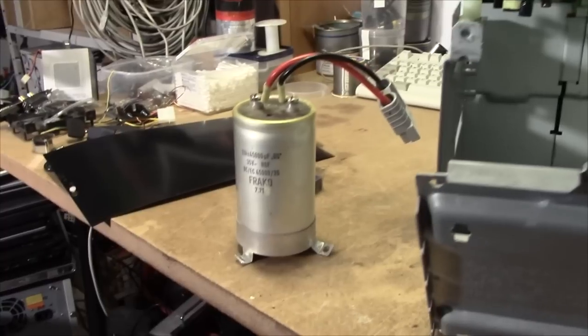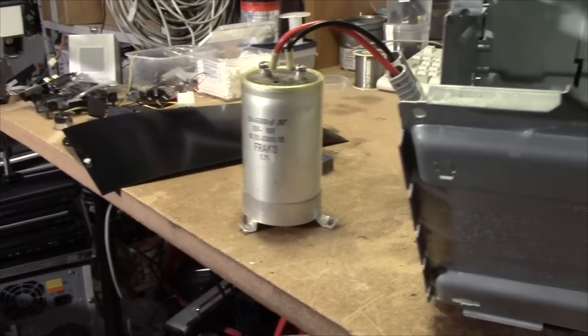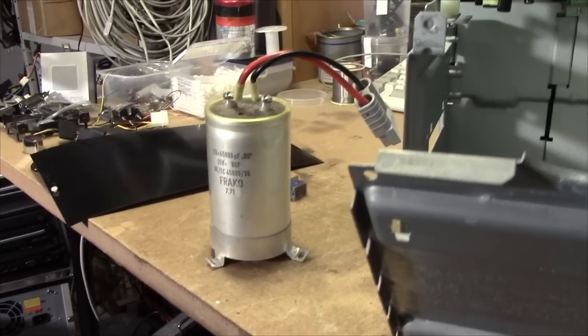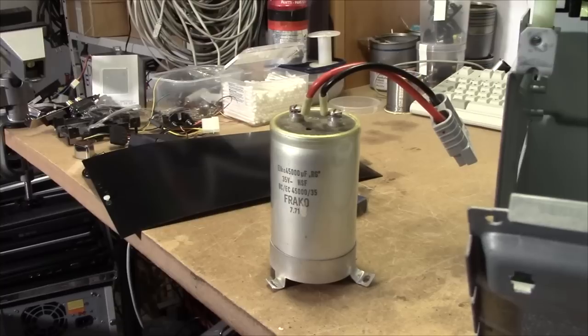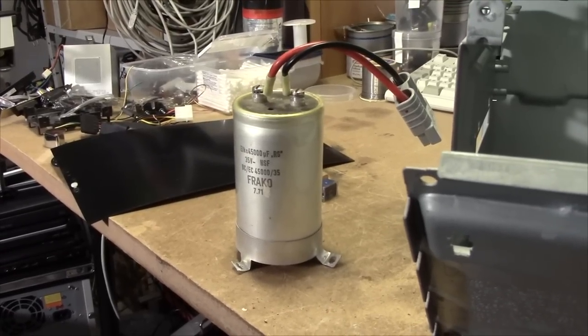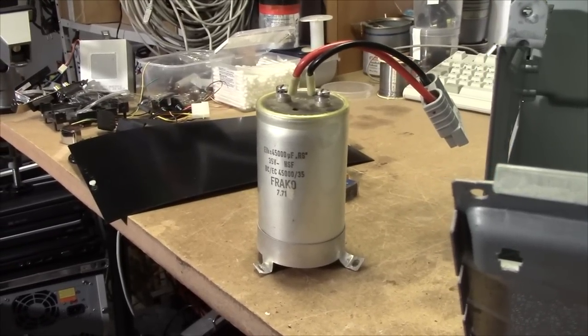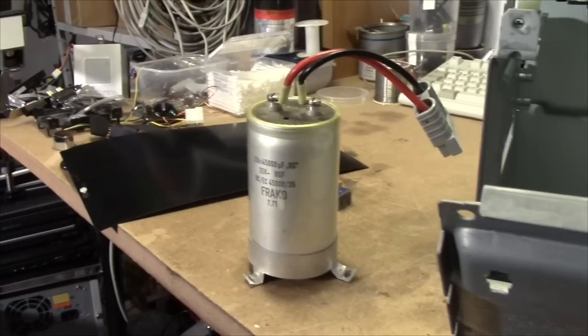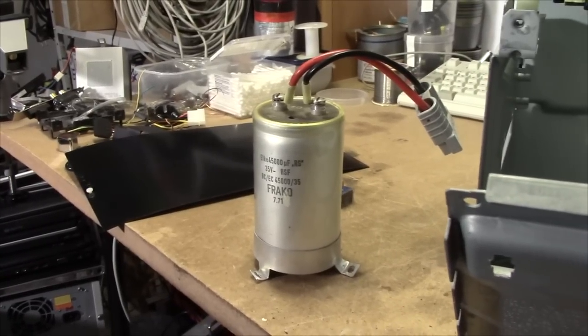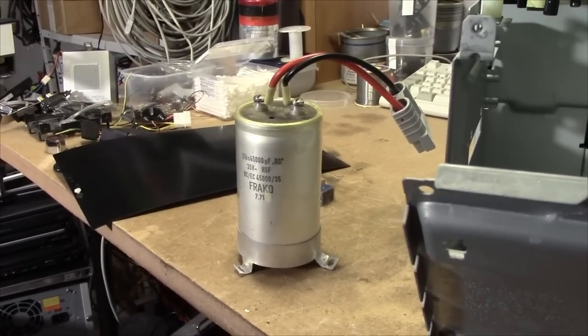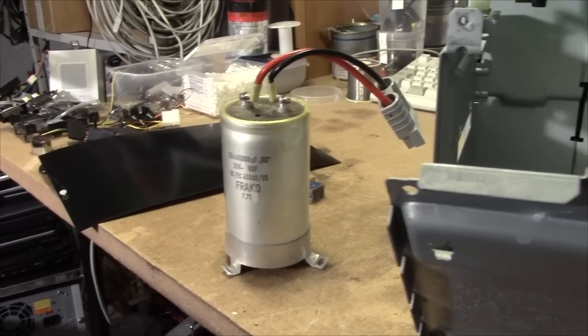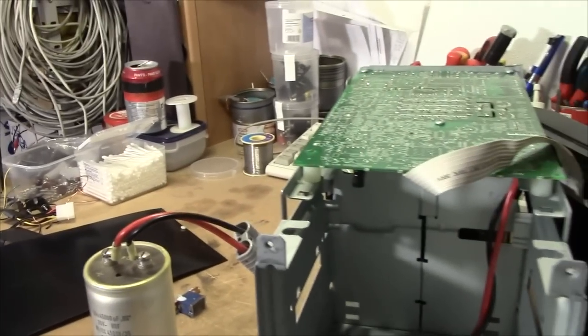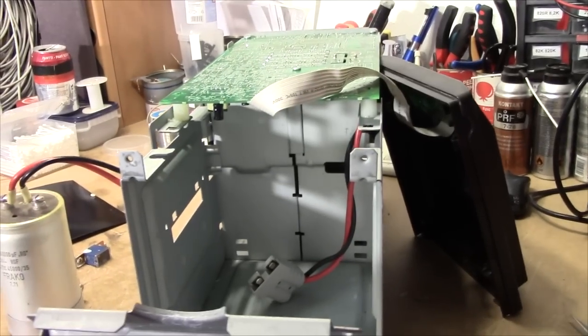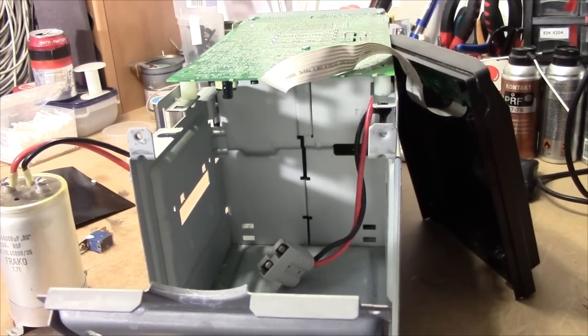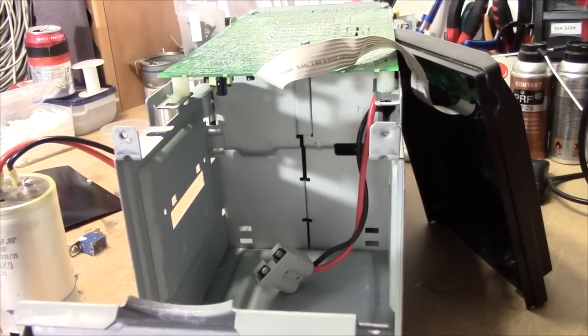The problem you get when you put too high a charging voltage isn't sulfation, because that's what happens when you discharge a battery too much. You get corrosion and overpressure as the electrolyte boils away and you essentially get too much acid in the batteries. That will just make the ESR of the battery go to hell, and everything will get hot and the batteries will warp, and then finally the UPS won't even turn on with these batteries because their ESR is too high, I can't detect them.